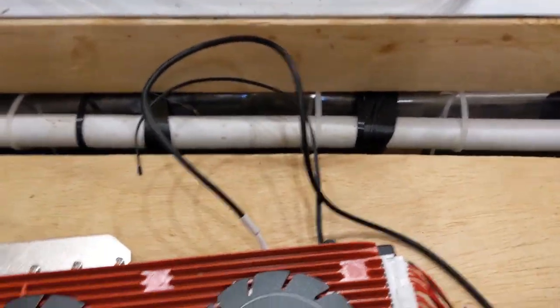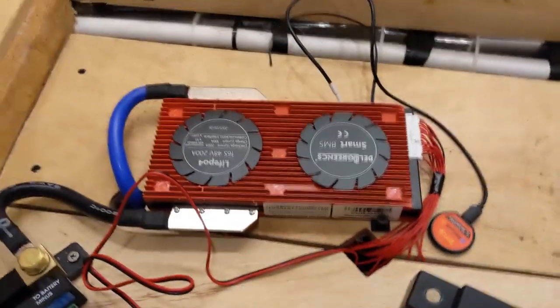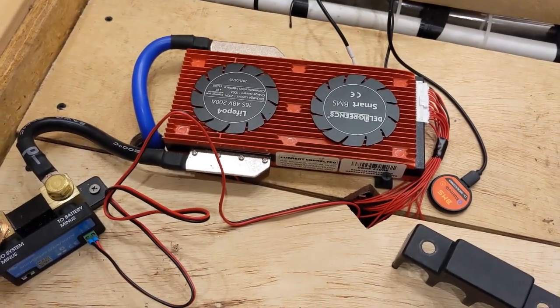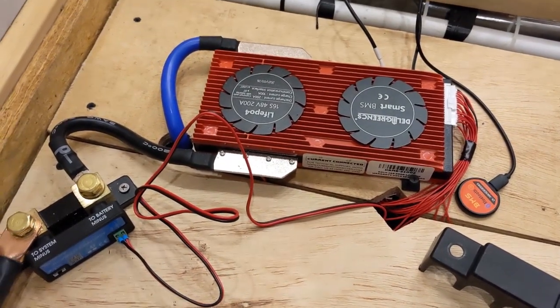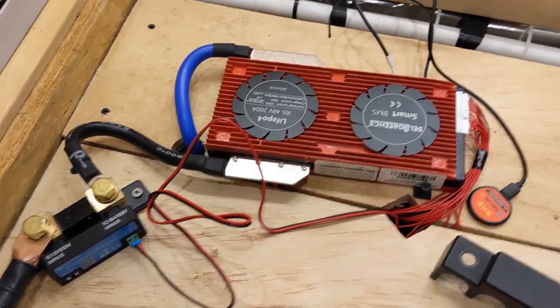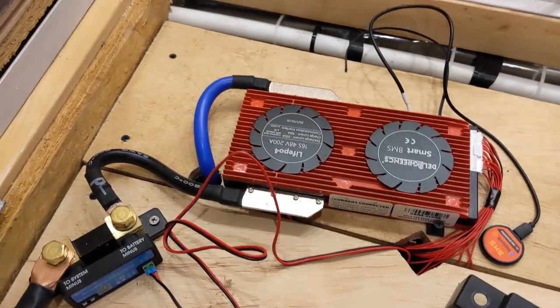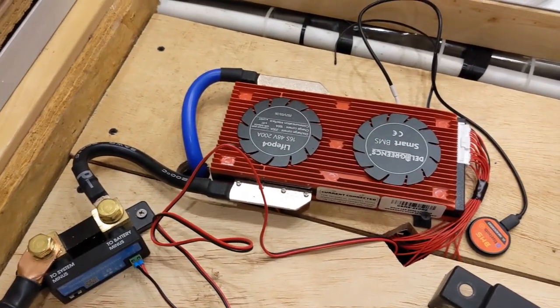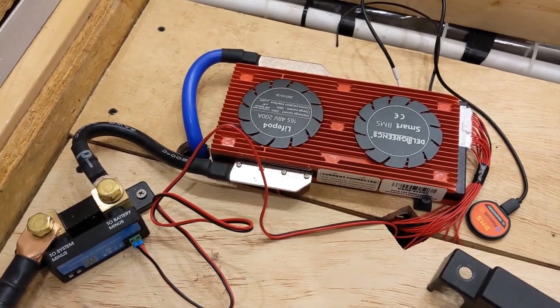And this is the temperature sensor for the battery management system. So what I need to do now is hook up the DC side of the inverter after checking voltages with the switches turned on and see where we're at as far as the installation goes. Hopefully I get the right voltages and we're ready to connect the inverter.